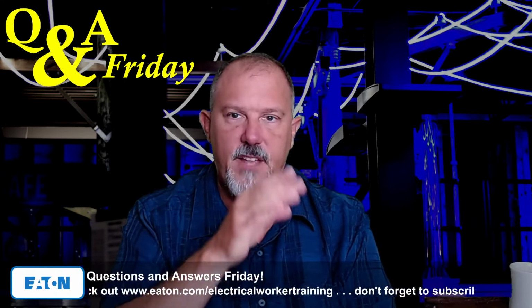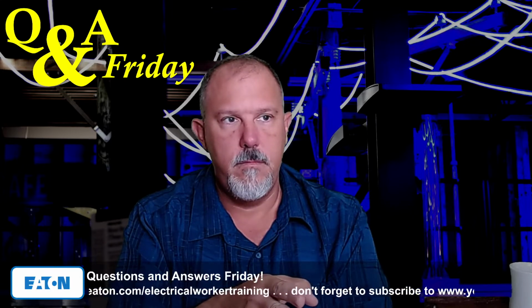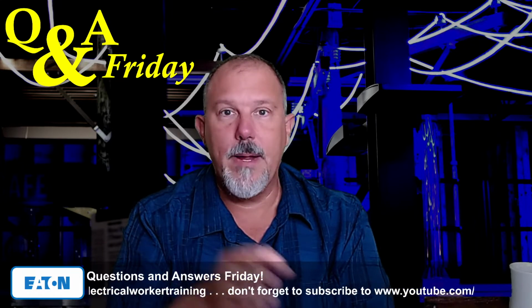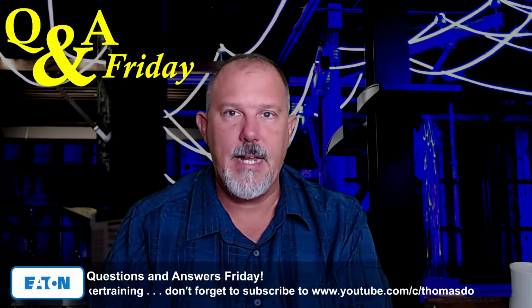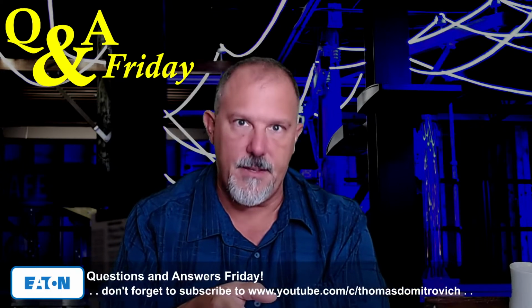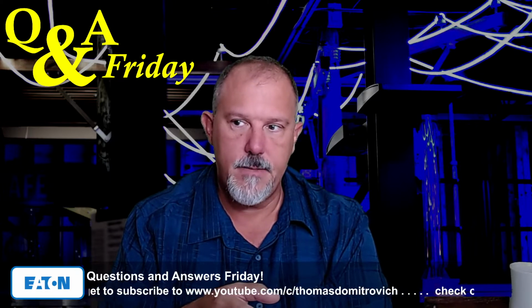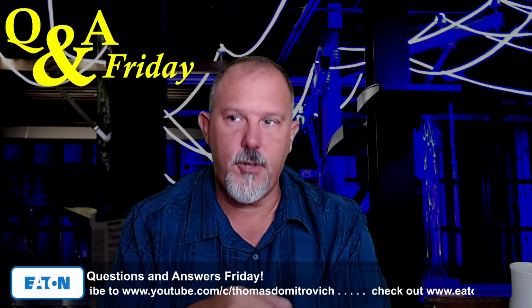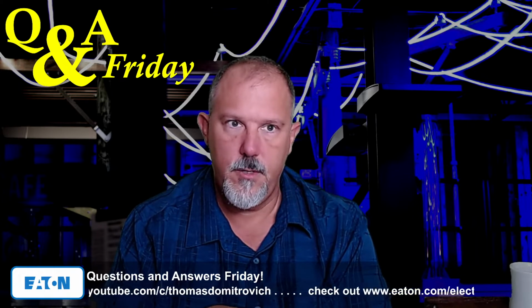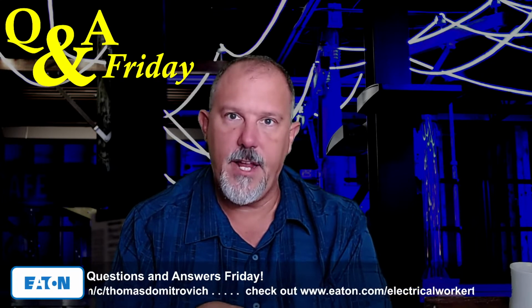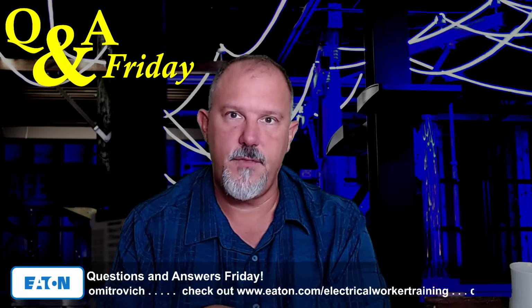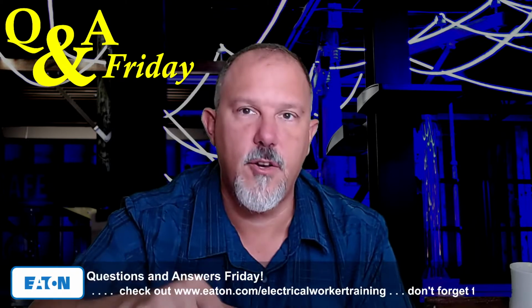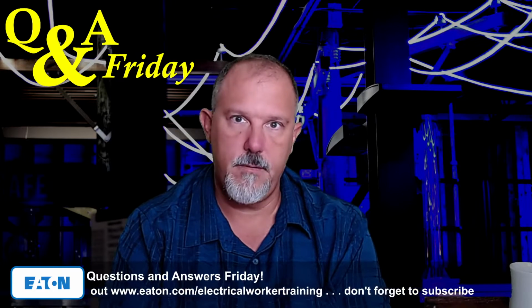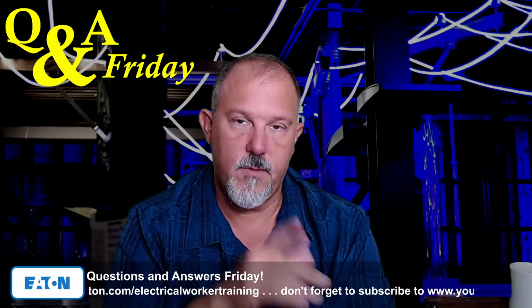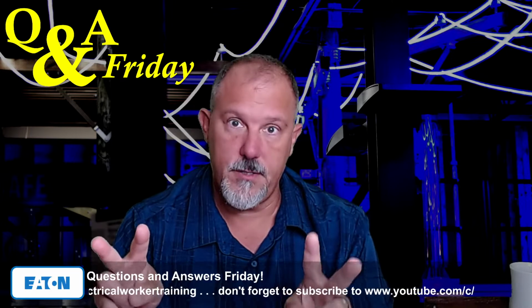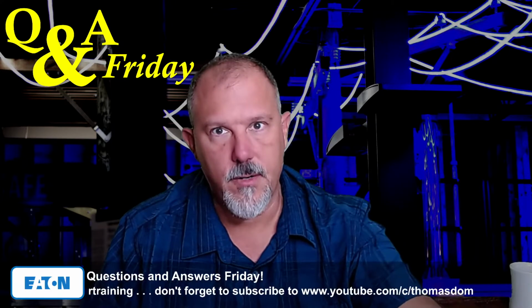And what you're saying is if you took a breaker that was a higher ampere rating and adjusted it down, could you do that? Well, I would argue, John, that you don't have an 80% rated application if you do that. You don't have a 100% rated application if you do that. Because, remember, I can get there two different ways.